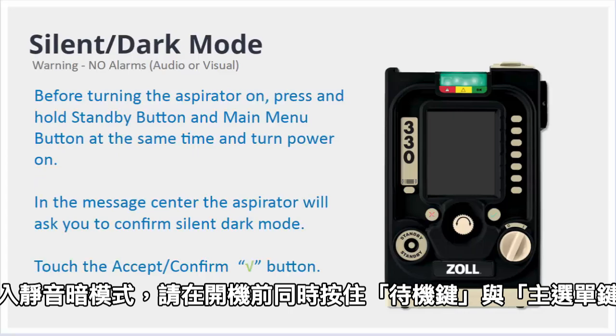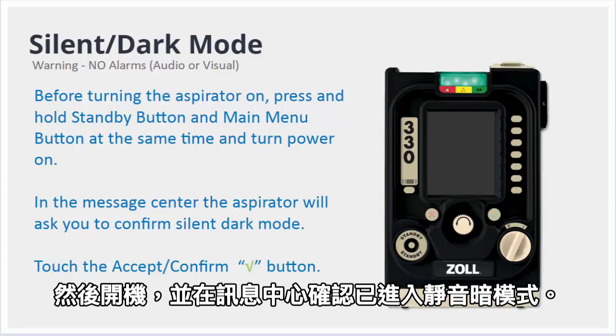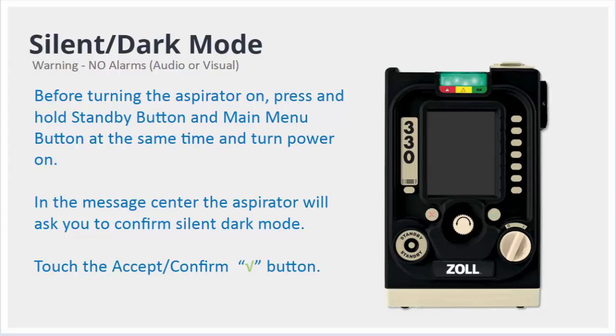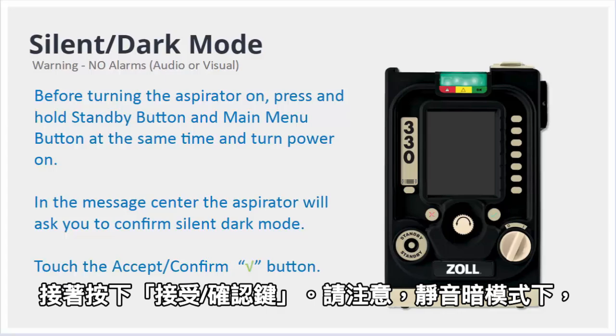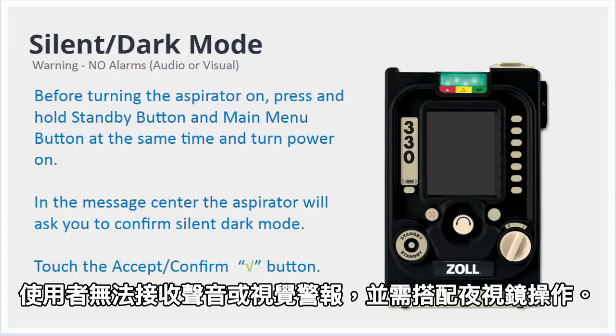To enter silent dark mode, before turning on, press and hold the standby button and the main menu button at the same time. Turn power on. In the message center, confirm silent dark mode. Then press the Accept Confirm button. Please note, during silent dark mode, the user has no audio or visual alarms and must use night vision goggles.